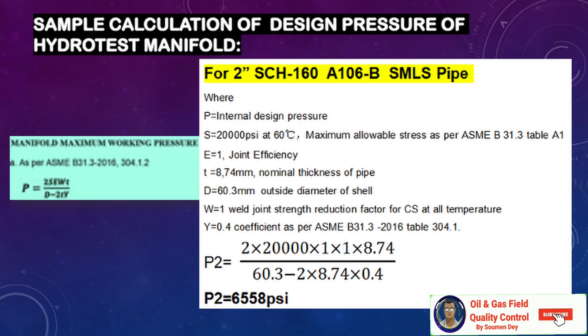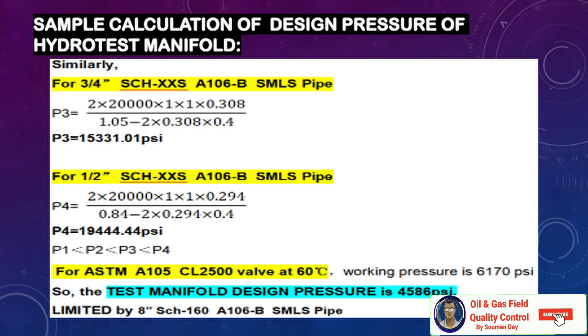Similarly, the calculation for 2-inch schedule 160 pipe gives 6,558 psi. For a 3/4-inch schedule XXS nipple, it can handle 15,331 psi. For 1/2-inch schedule XXS it can handle 19,400 psi. An ASTM A105 class 2500 valve at 60°C has a working pressure of 6,170 psi per the ASTM standard. Using these fittings, the manifold design pressure is 4,586 psi, limited by the 8-inch schedule 160 A106 Grade B pipe.